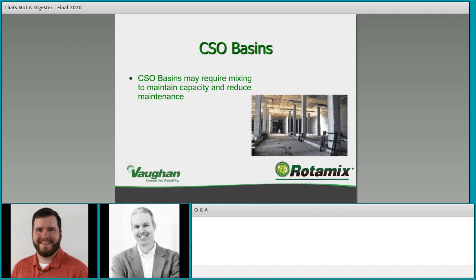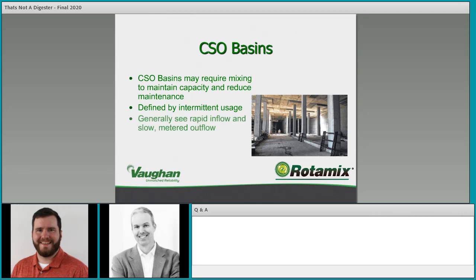CSO basins may require mixing generally to maintain capacity and reduce maintenance. CSO basins are defined by intermittent usage — you only use them during high-flow periods. They see rapid inflow and a slow metered outflow. Everything rushes in very quickly, very turbulently, carrying a lot of grit, solids, and debris from storm sewers. Then it's detained for a period of time, slowly metering out, giving time for things to settle and take away capacity.